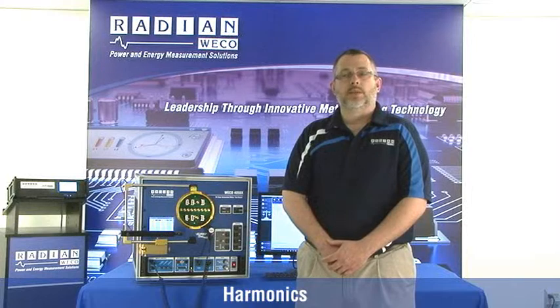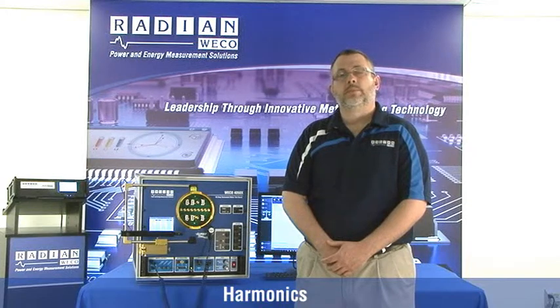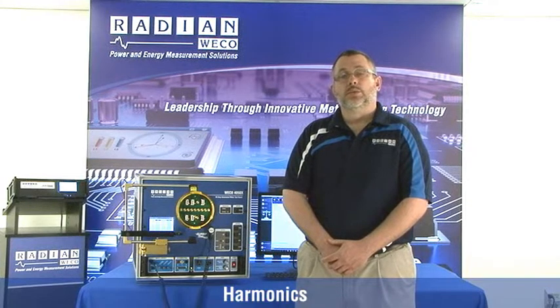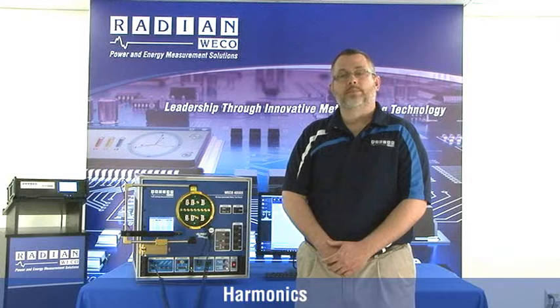So what is the utility industry doing to ensure they are properly metering these loads? Let's give an example of a customer complaint that harmonics are the cause of improper billing at a large load industrial customer. Typically, a utility will go on site for customer load or phantom load testing, or pull the meter and test back at the meter shop.